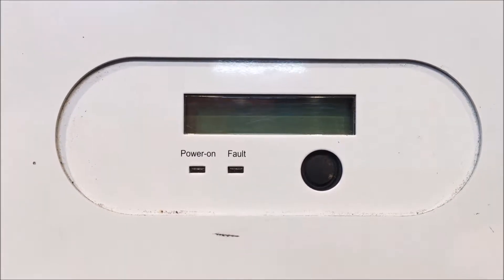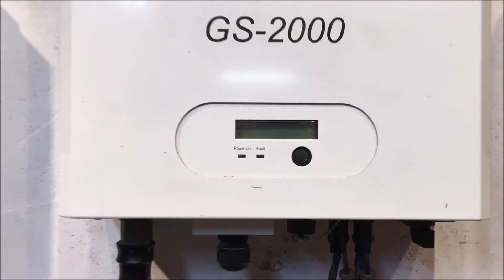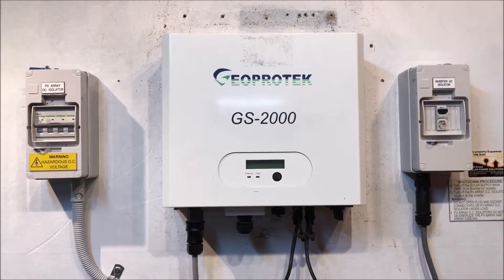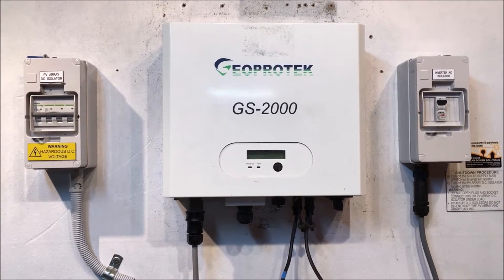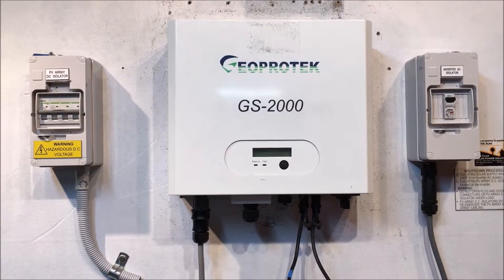What that's telling us with a Geoprotek inverter — and with most inverters actually — is that it's not detecting any power from the solar panels. It thinks it sees no power from the solar panels, so it thinks it's nighttime, and it's totally shut down. So if your inverter is coming up like this, there are a few things you should check.